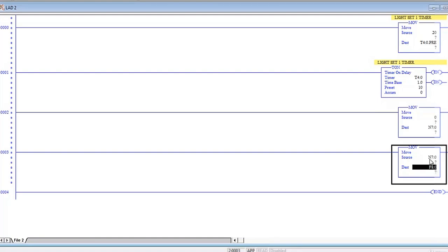So by going into an integer, multiplying by 10, and then coming back into a float, we can effectively round to the tenths place, or to the hundredths place if we multiply by 100, and so on and so forth. So there are definitely some instances where you'll have to do something like that and recast an integer as a float or vice versa, and the move command is good for that as well.